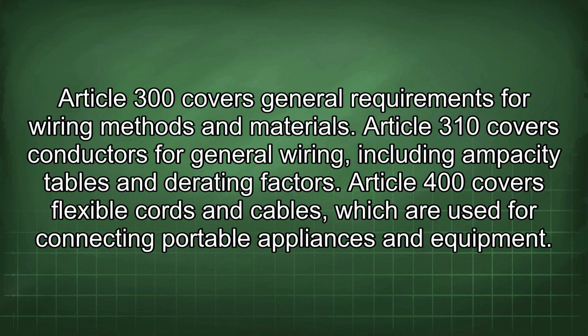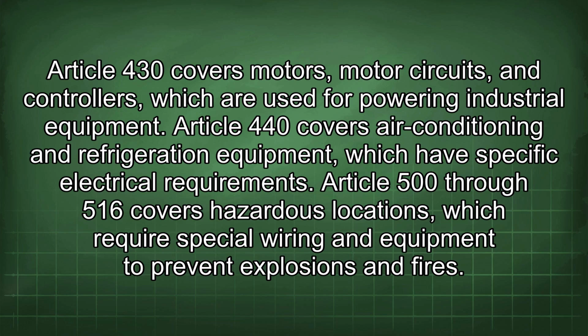Article 300 covers general requirements for wiring methods and materials. Article 310 covers conductors for general wiring, including ampacity tables and derating factors. Article 400 covers flexible cords and cables, which are used for connecting portable appliances and equipment. Article 430 covers motors, motor circuits, and controllers, which are used for powering industrial equipment. Article 440 covers air conditioning and refrigeration equipment, which have specific electrical requirements. Articles 500 through 516 cover hazardous locations, which require special wiring and equipment to prevent explosions and fires.